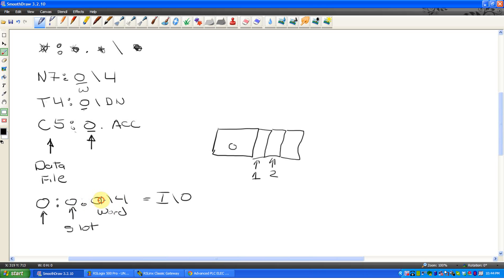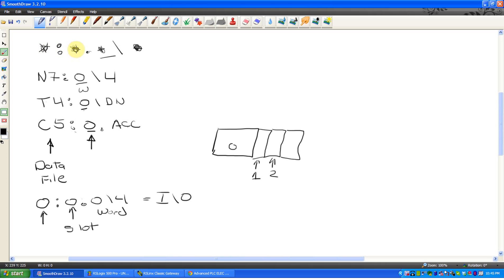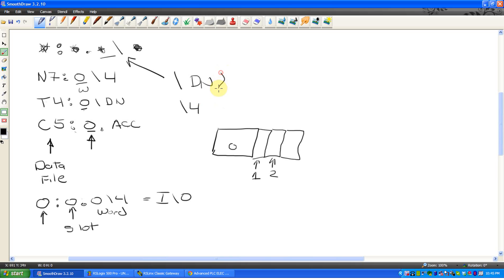So this only applies to real IO. So real inputs and outputs would have slot dot word, but you notice the pattern. Dot word here dot word here dot word. If you see something, something colon, the first something is the data file, after the colon is either going to be slot or word, and then when you see a slash, anything after a slash, so you see slash DN or slash four, these are always referred to as the bit. If it's after a slash, it's bit level. So slash something is bit before the colon's data file.